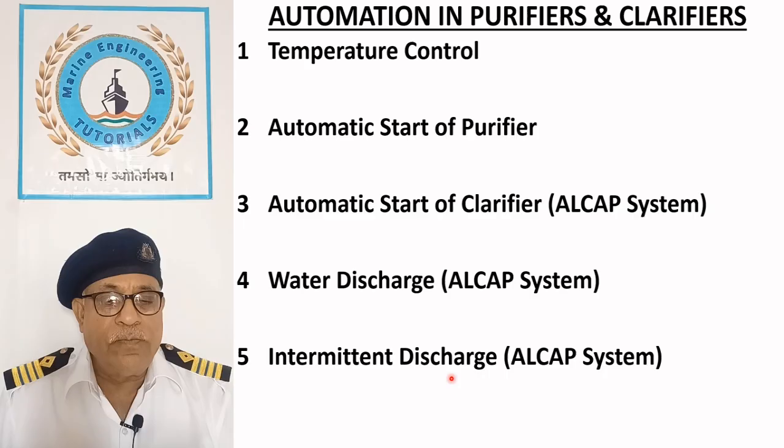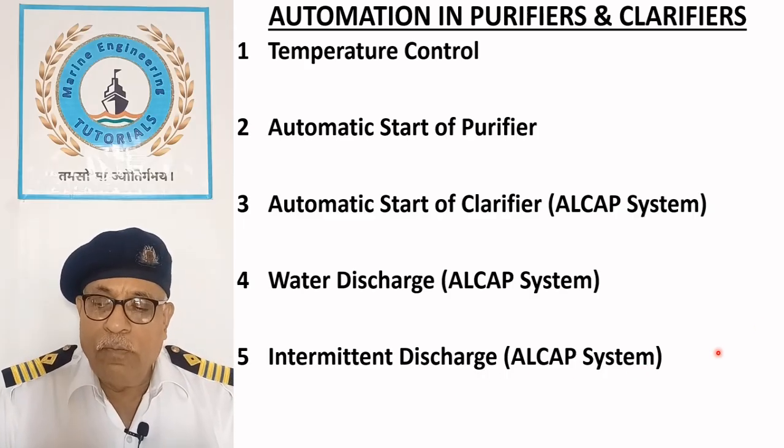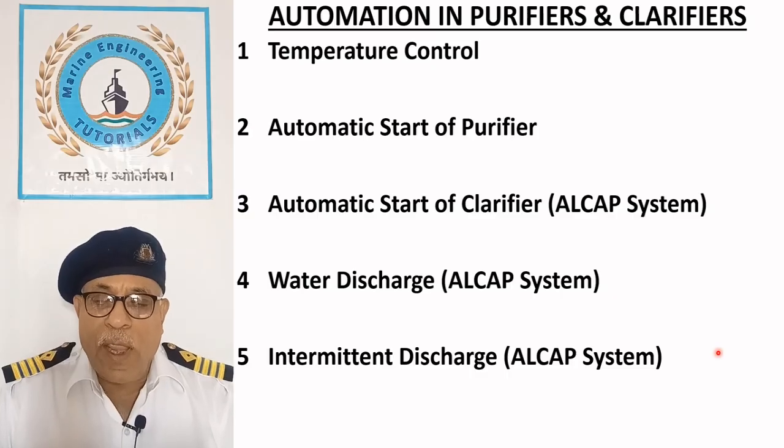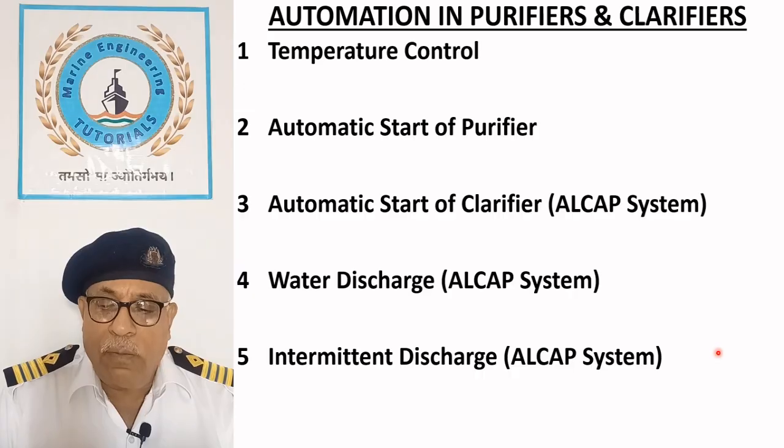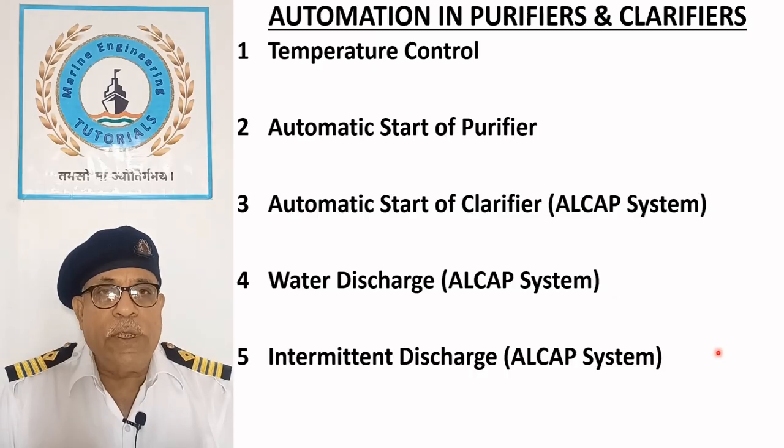Intermittent discharge in ALCAP system. As per the set interval, the controller supplies valve opening water through the solenoid valve for a short duration to discharge sludge intermittently without stopping the oil feed.